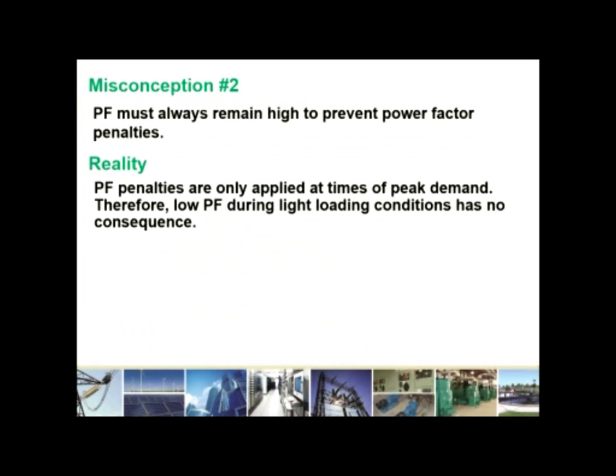So misconception number 2 is that power factor must always remain high to prevent power factor penalties. And the reality is that power factor penalties are only applied at times of peak demand. Therefore, low power factors during light loading conditions will have no consequence.